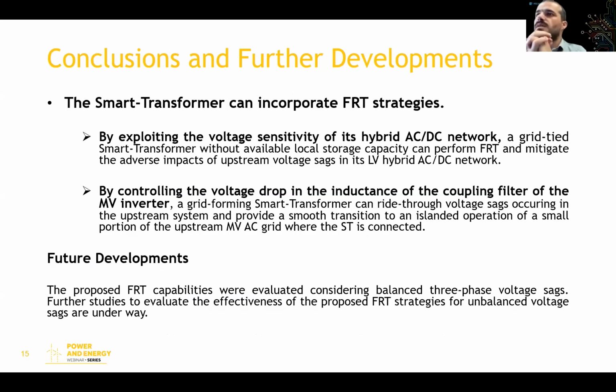So that's it. Based on this work, it was possible to conclude that the smart transformer can indeed incorporate fault ride-through strategies. For the case of a smart transformer without storage available, we can successfully exploit the voltage sensitivity of its hybrid AC-DC network. And for the case of a grid-forming smart transformer, which we want to use to support a small section of the upstream medium voltage network, it was also demonstrated that it can successfully withstand the voltage sag in the upstream system and then transit to the island mode without power interruption.